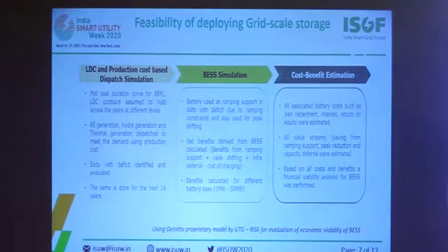We analyzed our load duration curve across different levels in a year, then did dispatch simulation for thermal and hydro generation, considering RE as a must-run plant. We found the slots where we have a deficit for ramping up, then simulated the battery energy storage system with those load duration curves and dispatch simulation to find the ramping requirement that can be met through BESS.